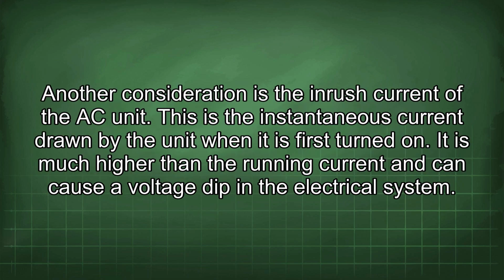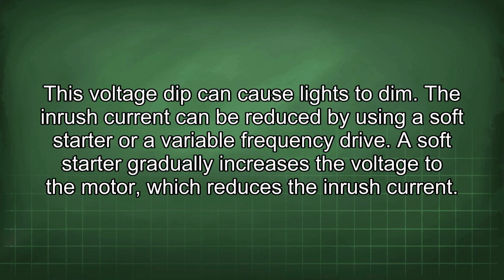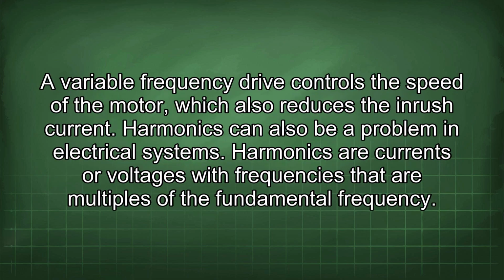Another consideration is the inrush current of the AC unit. This is the instantaneous current drawn by the unit when it is first turned on. It is much higher than the running current and can cause a voltage dip in the electrical system. This voltage dip can cause lights to dim. The inrush current can be reduced by using a soft starter or a variable frequency drive. A soft starter gradually increases the voltage to the motor, which reduces the inrush current. A variable frequency drive controls the speed of the motor, which also reduces the inrush current.